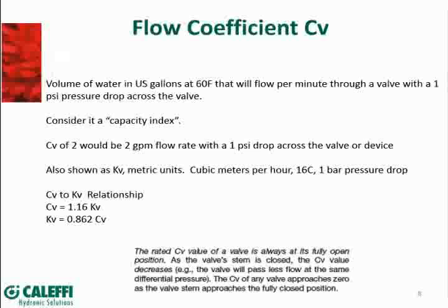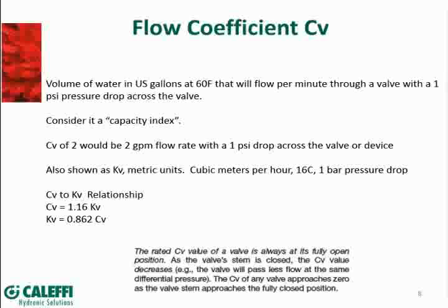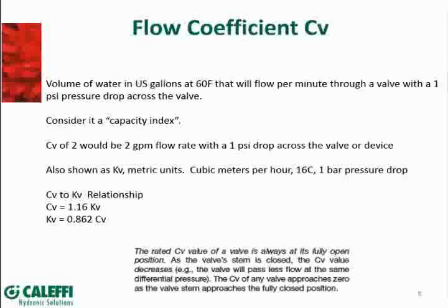Most of the information I found came from manufacturers of valves and components. When we talk about CV, it not only applies to water-based systems today — it also applies to liquids, vapors, saturated steam, and even pneumatic controls and devices. So I'm barely scratching the surface on what's involved in this whole flow coefficient discussion. Basically what we've got is the volume of water in U.S. gallons at 60 degree Fahrenheit that will flow through a valve or device — and that could be a separator or something like that — with a one PSI pressure drop across it.